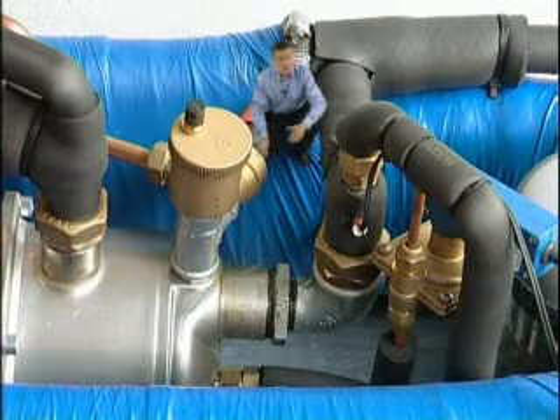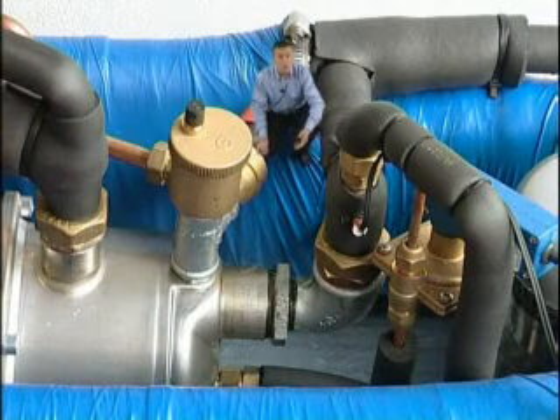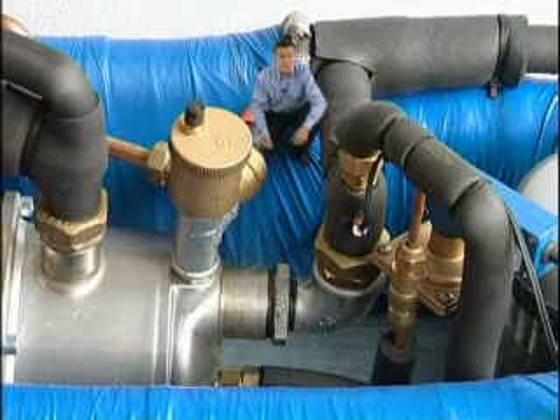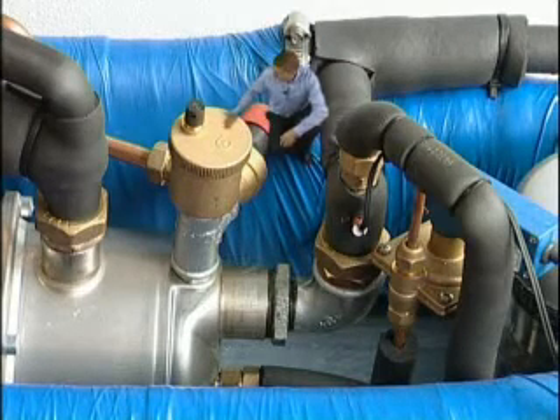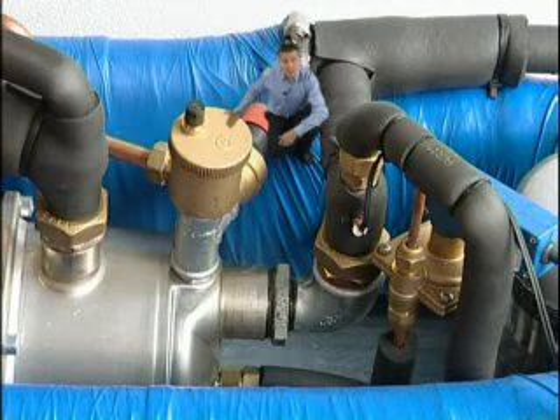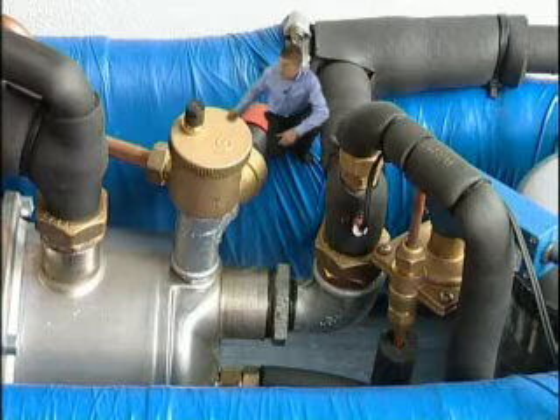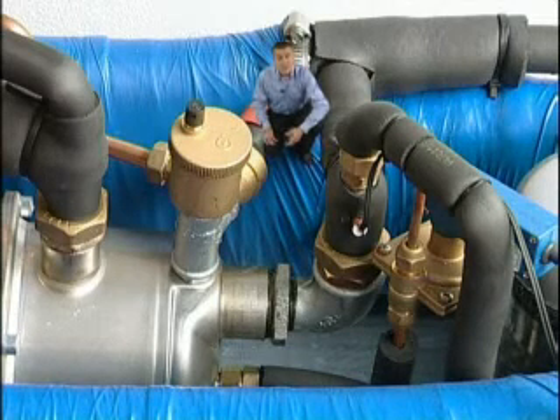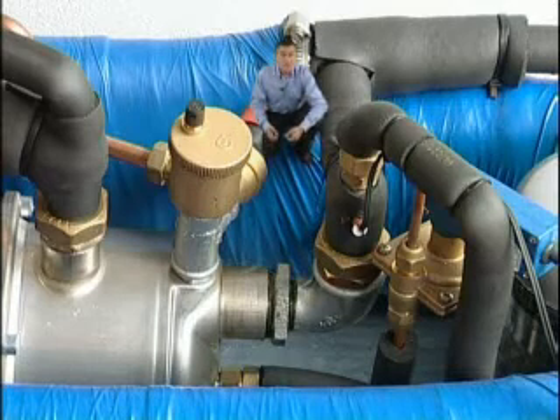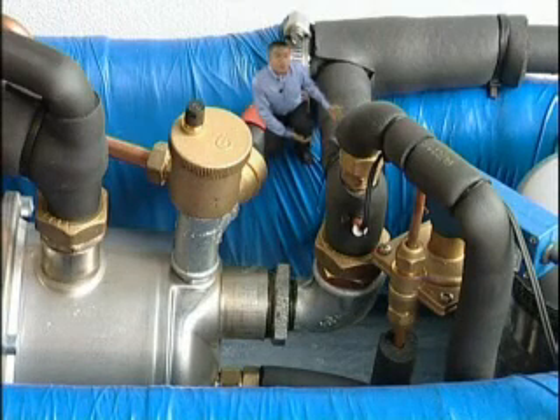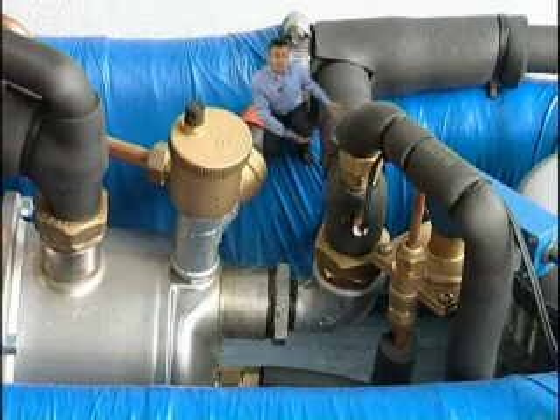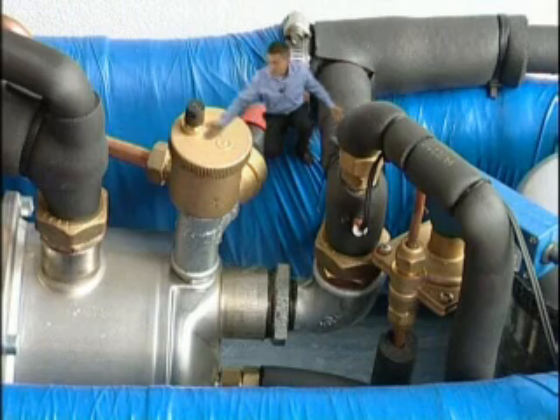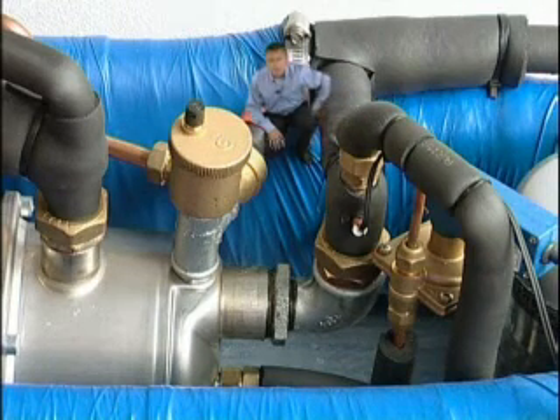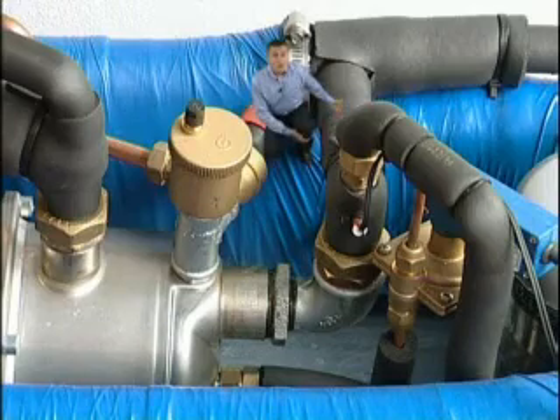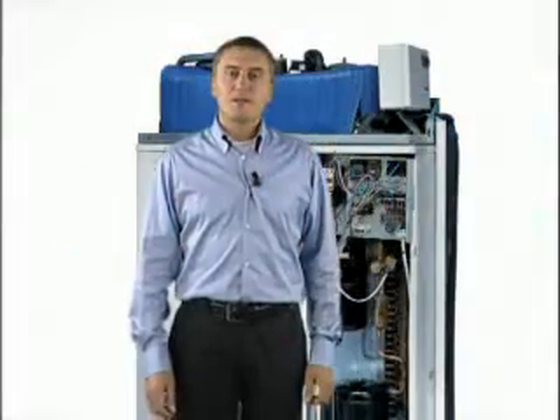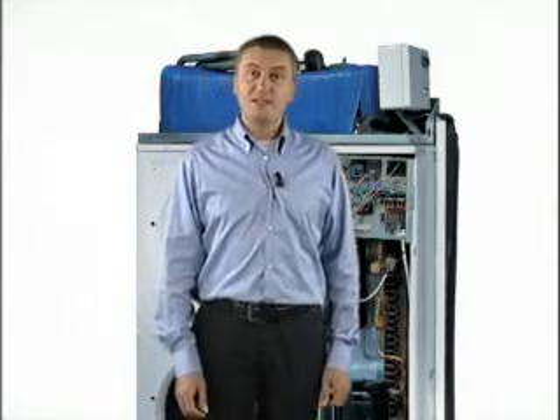Continuing our journey inside the Climabox, we finally see two components which are highly important for the good working and the safety of the machine. Here we can see the automatic air bleed that permits the discharge of air within the system. And for increased safety and good working of the machine itself, to my left, the differential pressure switch, which guarantees the correct functioning of the pump, the circulation of the water in all directions within the machine itself, and allows high machine performance. We are at the end of our small journey inside Climabox.